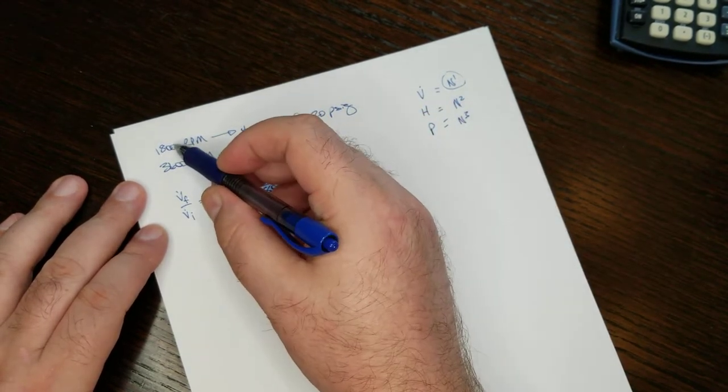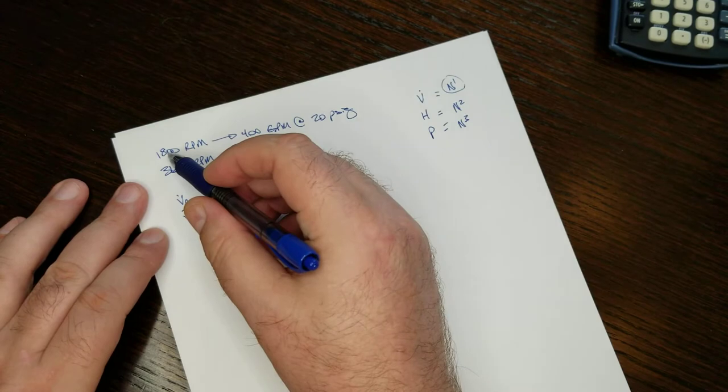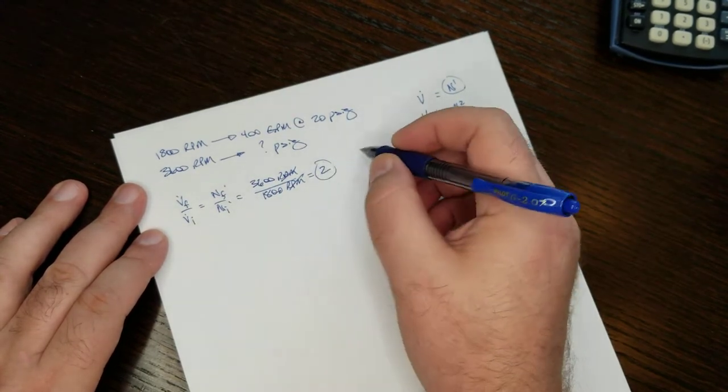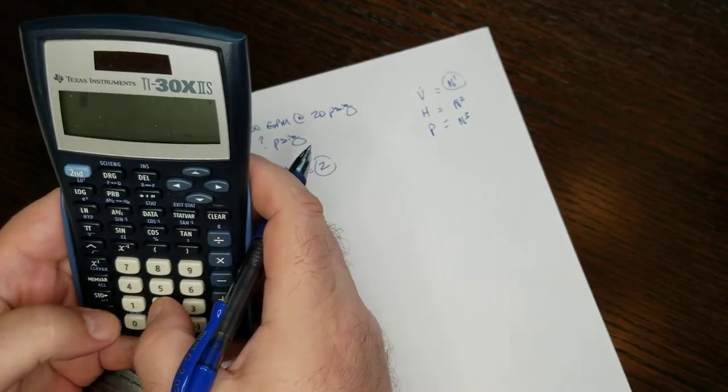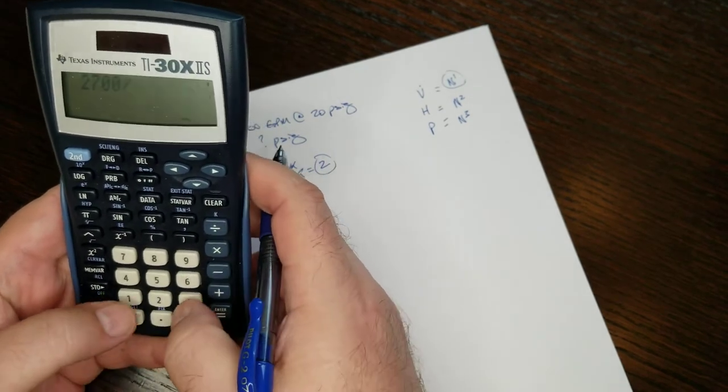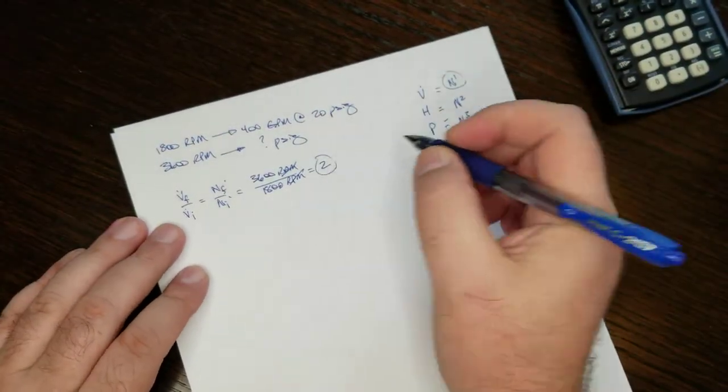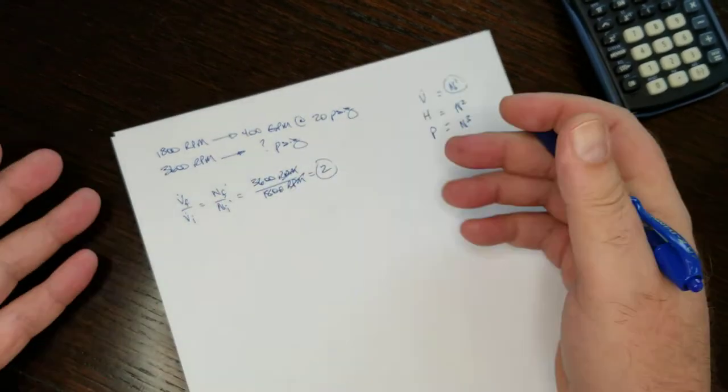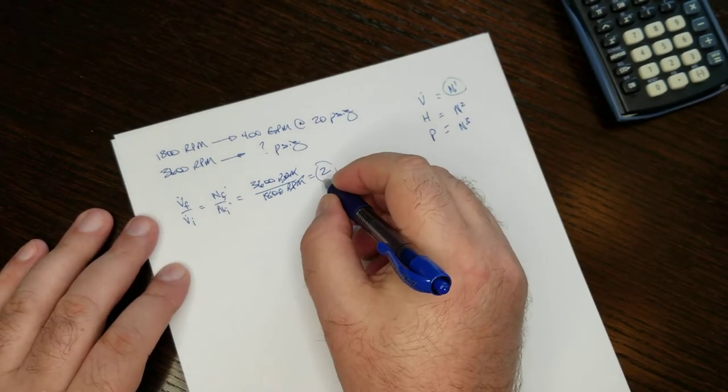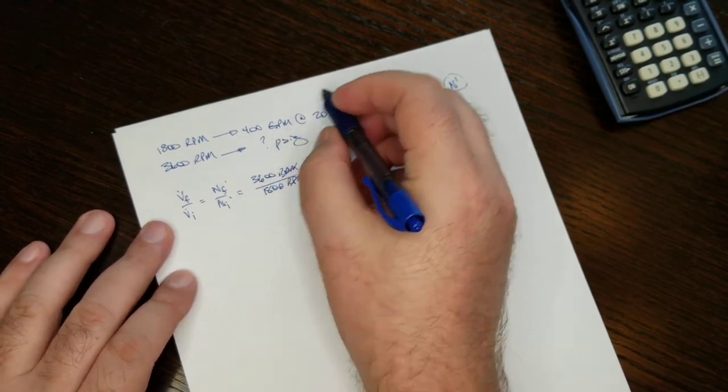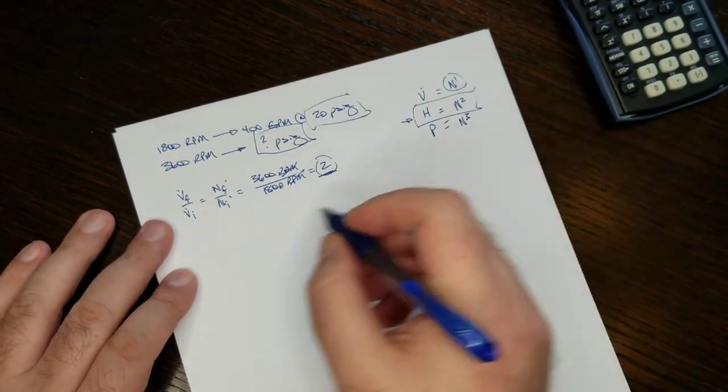If it had changed by half again as much, instead of 1800 to 3600, if it had only gone up by 900 rpm and was 2700 rpm, then it'd be... let me do that math. Don't do that in my head. Give me a sec. 2700 divided by 1800, 1.5. Yep. Then the factor would be 1.5. Whatever that factor is, that's what we use to figure out the pump head and the pump power. So we have a factor change of 2. What it's asking for is the discharge head, the head of the pump discharge pressure.